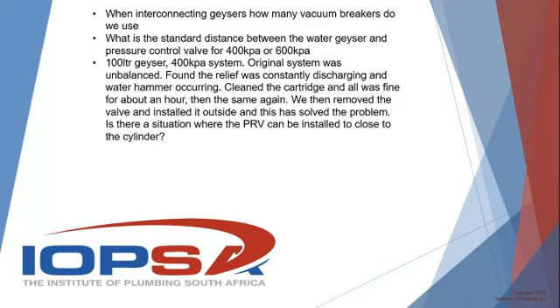So okay, good point. The unbalanced nature of the system meant that the valve was experiencing probably a little bit of back pressure, or there was a cross connection somewhere, and somehow or another, by moving that valve outside, they prevented that from happening for some reason. You know, plumbing is one of those things. It's a case-to-case basis, and everything will have to be looked at. But the question is, the answer is no. You can't have a PRV too close to the geyser.